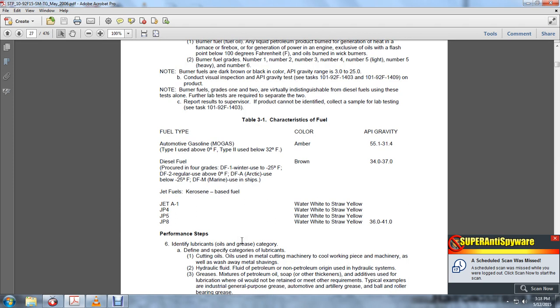Diesel fuel is procured in four grades: DF1 winter use to -25, DF2 regular use above 0 degrees Fahrenheit, DFA Arctic use below -25 degrees Fahrenheit, and DFM marine use on ships only. The color is brown and the API gravity is 34.0 to 37.0. Jet fuels are kerosene based. Jet A1 is water white to straw yellow. JP4 is also water white to straw yellow. JP5 is water white to straw yellow. JP8 is water white to straw yellow with an API gravity of 36 to 41.